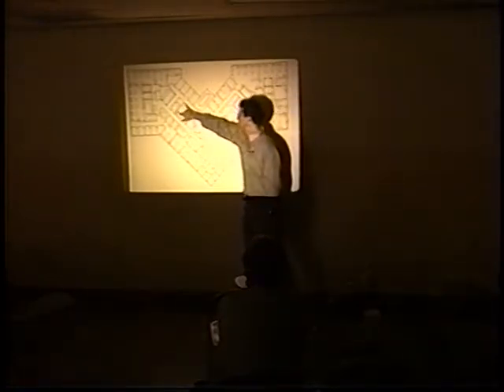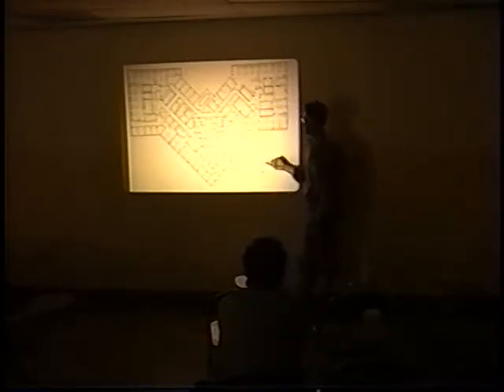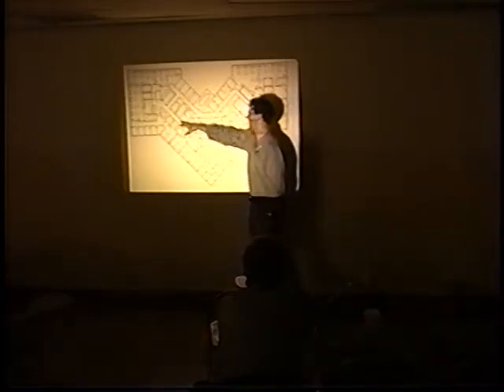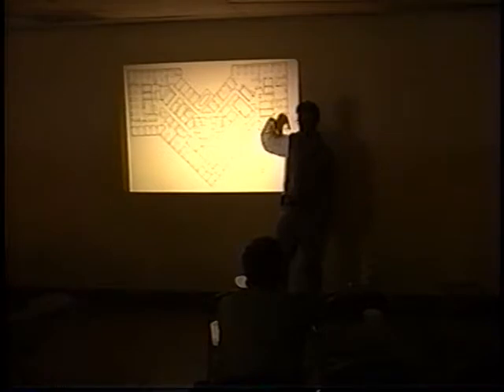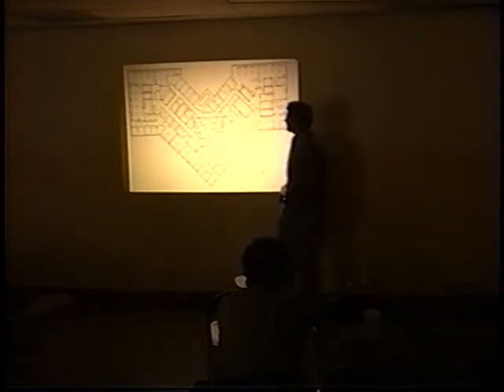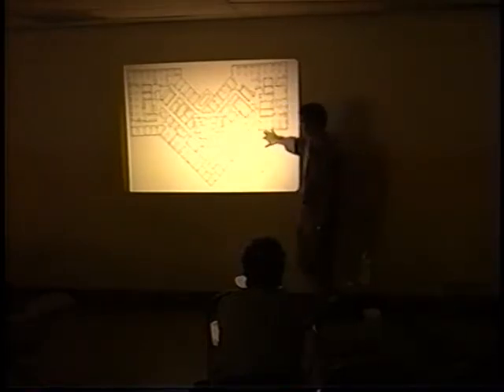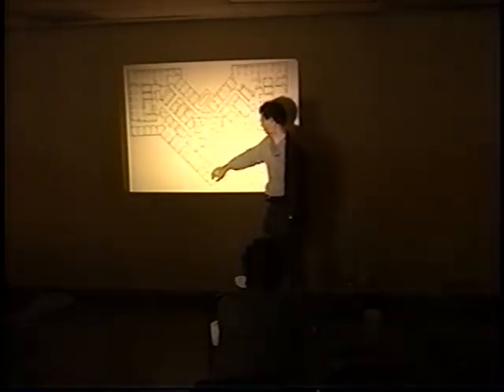And then within the core is a set of biological hazard rooms or clean rooms that do not need natural light, are not used all the time, and then need to be shared by different scientists in different laboratories. These are the kind of rooms that have what's called positive pressure, which is the heating, ventilation, and cooling creating a positive pressure within this space so that airflow continues to go out and does not allow contaminants to come in. In addition, on this floor, you'll have things like office suites that will service laboratories.